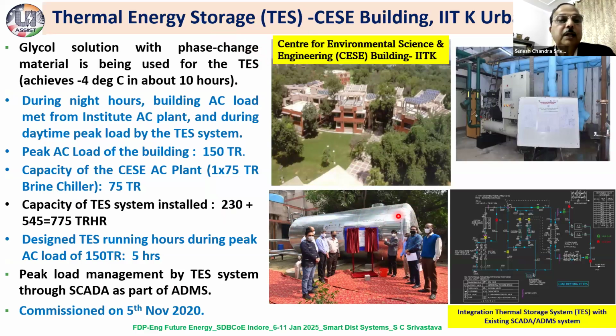We made it operational, 230 ton hour, and this other one is 545 ton hour. So total 775 ton hour we have installed. The basis was that the peak load is about 150 tons, so at least 5 hours we can run the air conditioning system through this once it is cooled down.